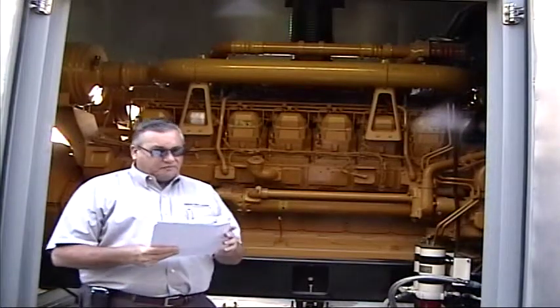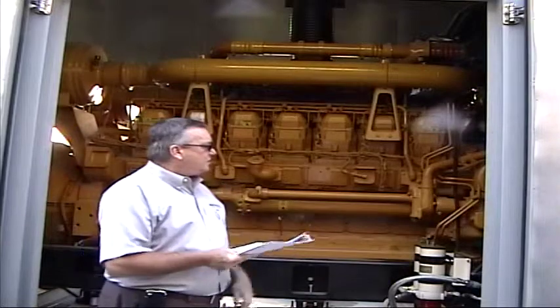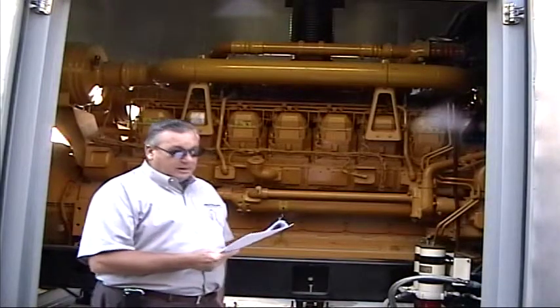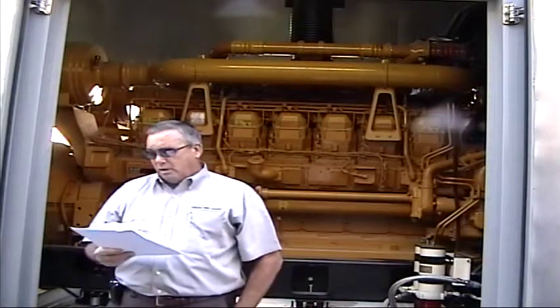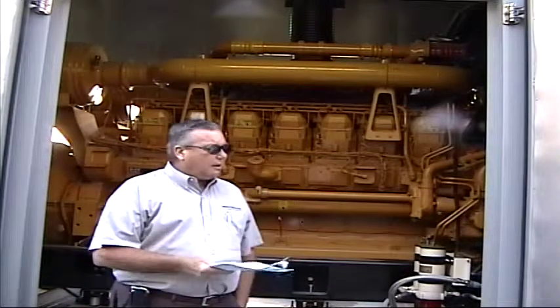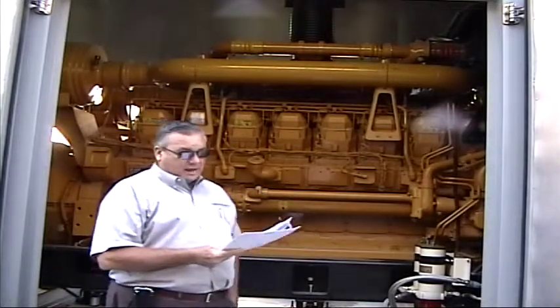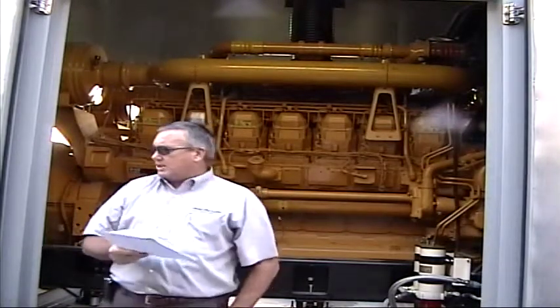At 75% load, you're at about 107, 108 gallons an hour, giving you 11+ hours of fuel. And at 50% load, you're at about 78 gallons an hour, that's 15+ hours.